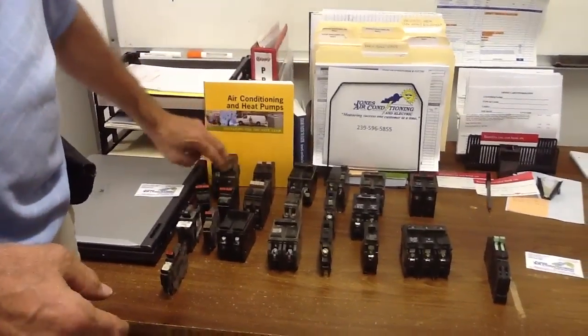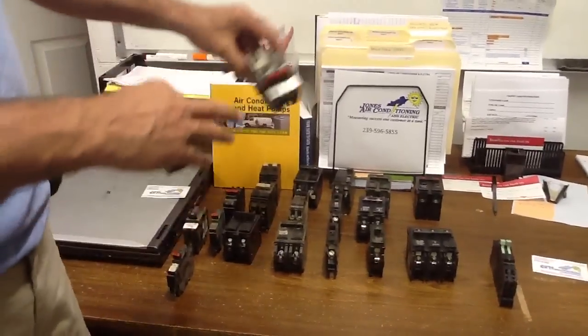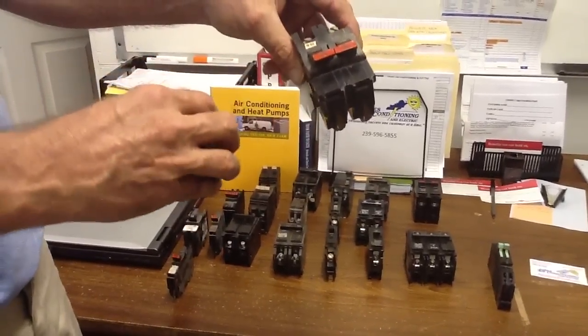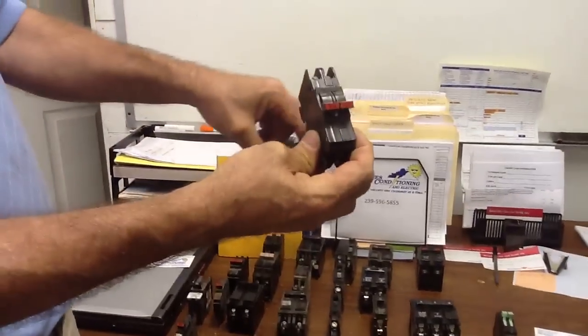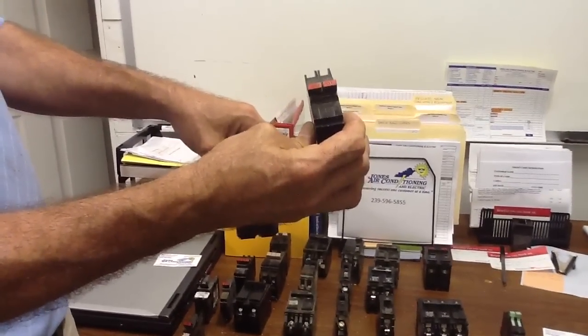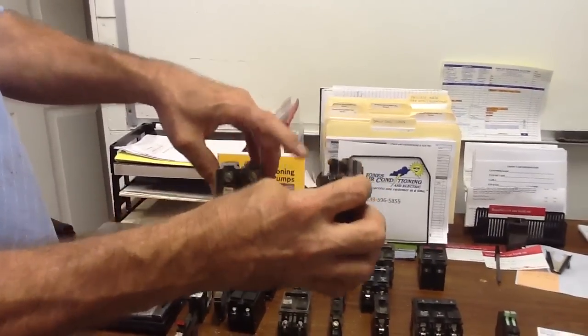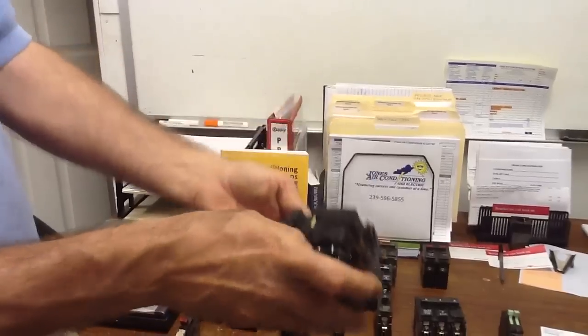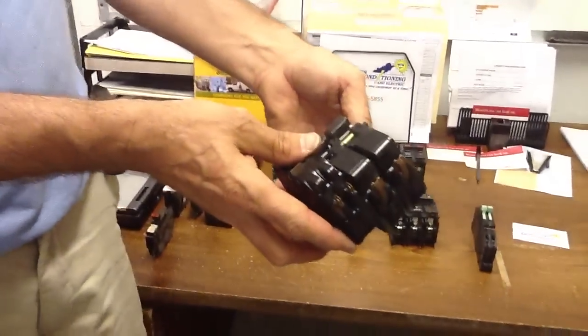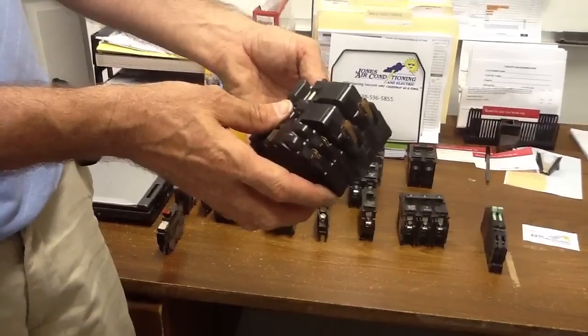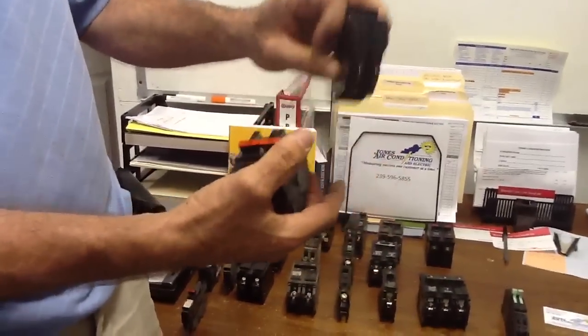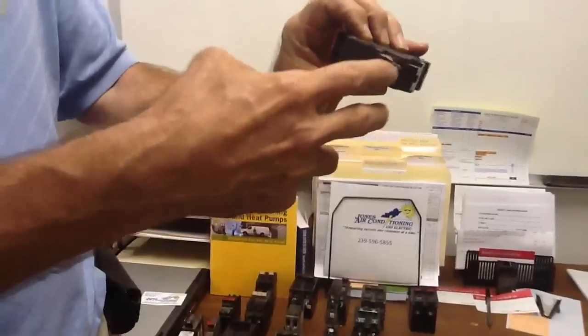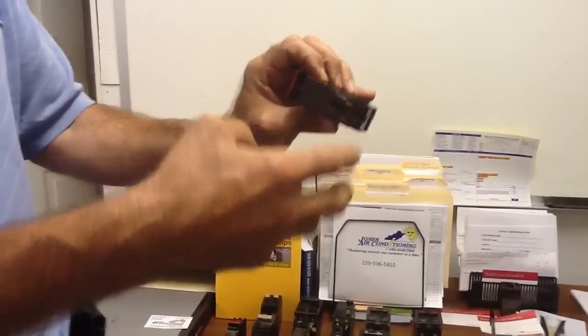Here is a, this is what we call a fat Federal Pacific breaker, double pole. This is a thin Federal Pacific breaker, double pole. They also have different type stab locks if you look, and you've got to be very careful how you put them on the bus bar, because this bus bar sits in two spaces. This bus bar sits in one space, so you have to actually straddle the bus bar.